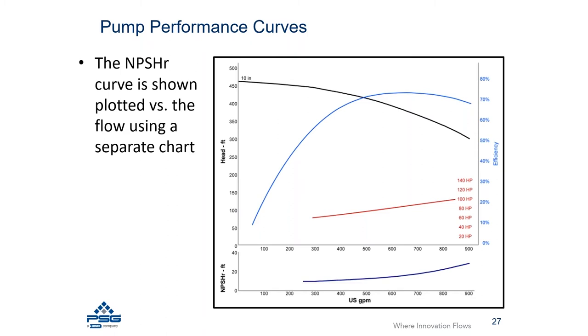Finally, there is another characteristic called NPSH required. The industry is starting to convert this term to NPSH3 — they mean the same thing for centrifugal pumps — though historically the nomenclature has been NPSHr. We have another webinar covering NPSH requirements in much more detail, but this is a characteristic of the pump that should be presented on a pump performance curve.